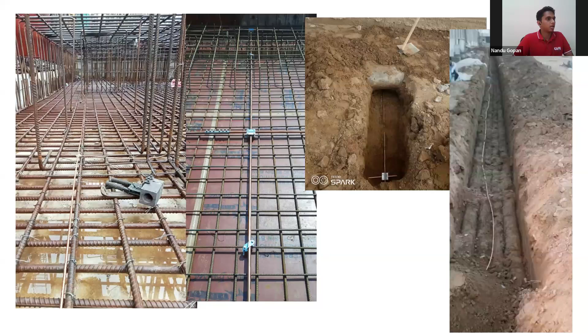Now on to the meshed earthing system. I would actually recommend the meshed earthing system, because the standard, the 60364 series of standards, recommends this. The National Electrical Code also recommends this type of earthing. So what it says is, you have building 1, you have building 2, and you have a few towers.